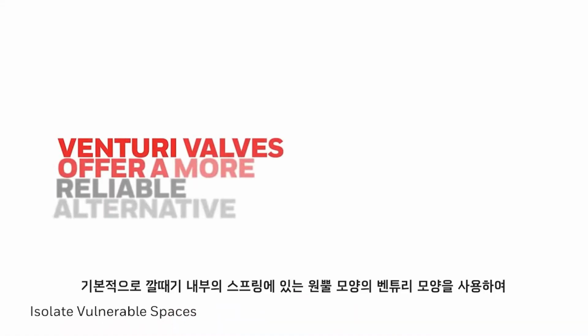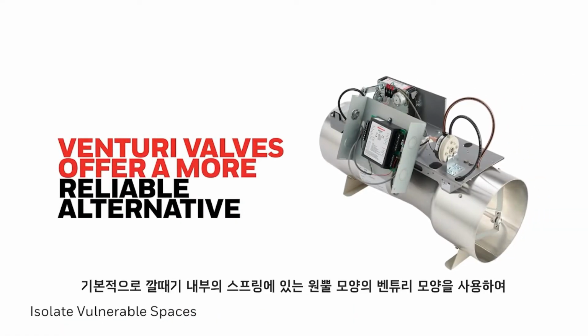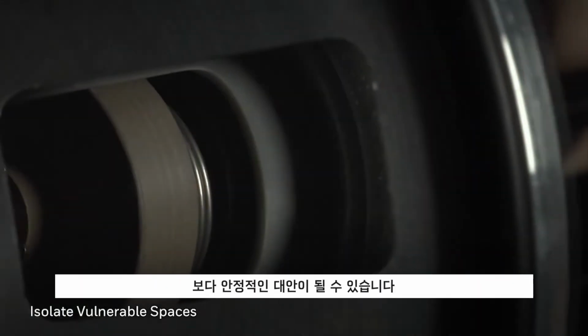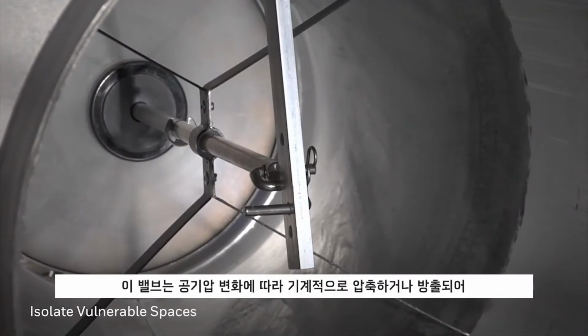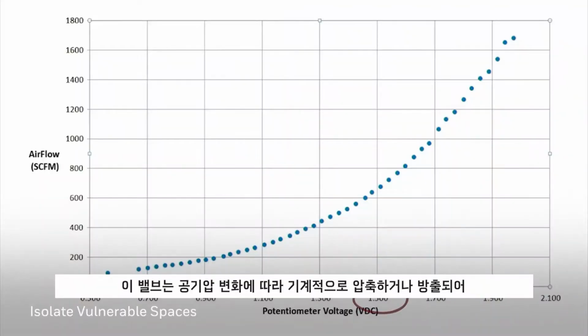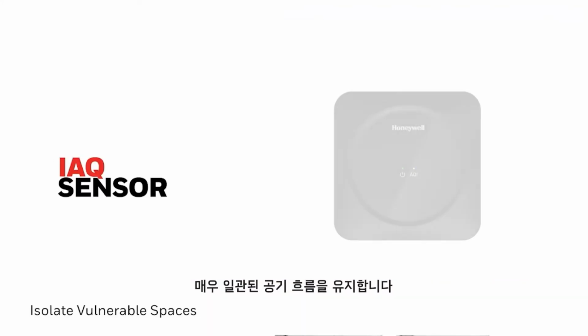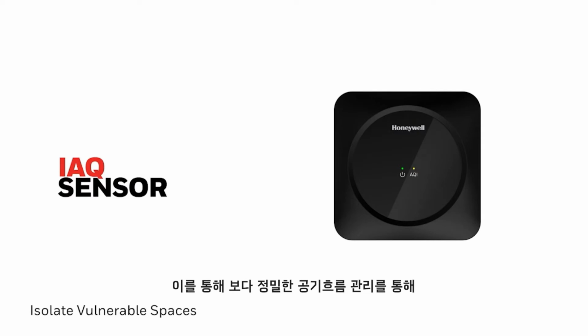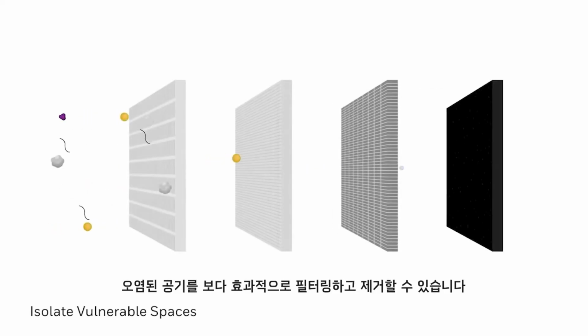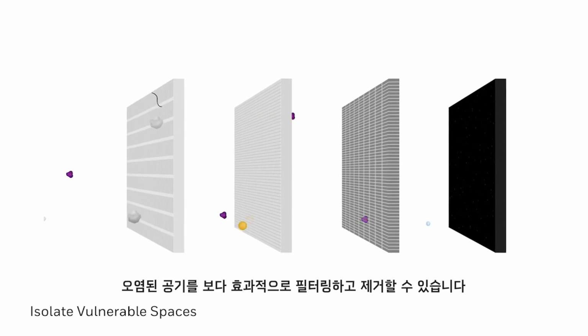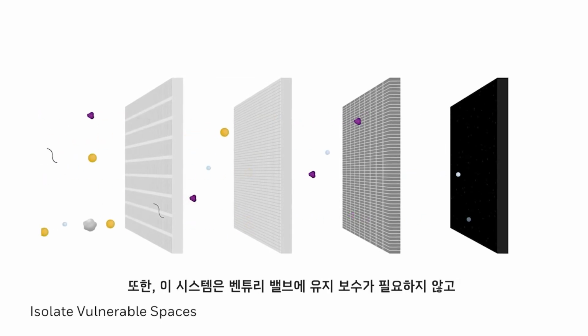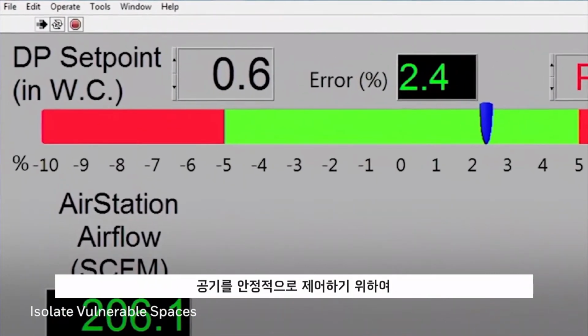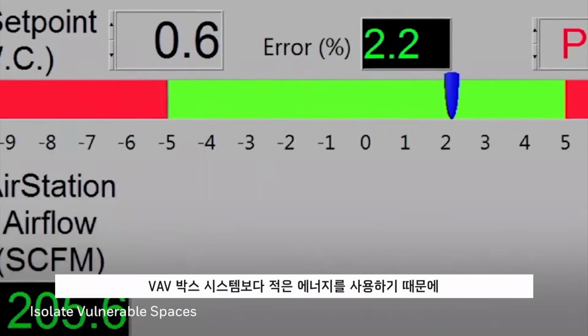A Venturi valve offers a more reliable alternative. Using a Venturi shape, essentially a cone and a spring inside a funnel, the valve mechanically compresses or releases in response to air pressure changes, maintaining very consistent airflow. This provides more precise airflow management, enabling more effective filtration and removal of contaminated air. This system is also typically more sustainable, since Venturi valves need no maintenance and use less energy than a VAV box system to control air reliably.